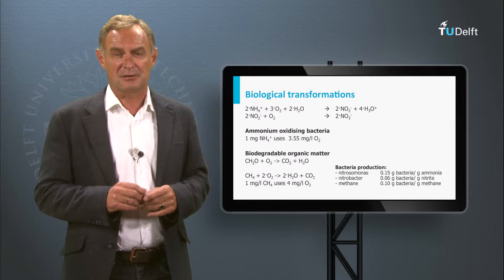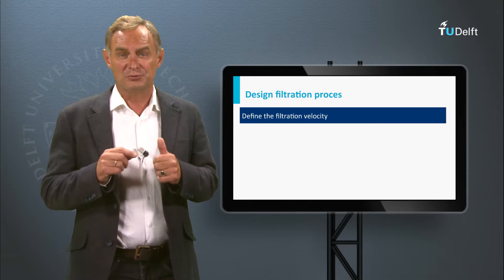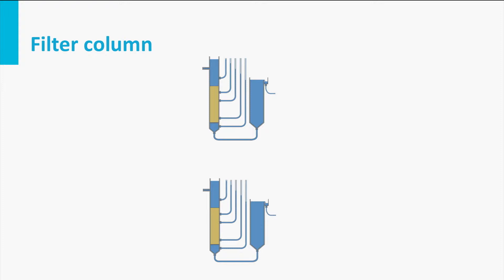To be able to design a filtration process, it is necessary to define the filtration velocity needed to know the total surface area required for filtration, the filter bed height, and the grain size of the filtering material. Therefore, pilot plant testing is performed.